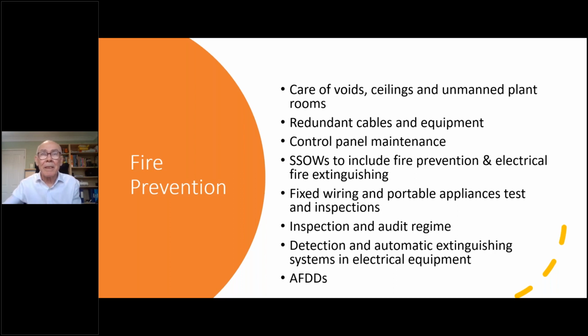So on fire prevention, a lot of what we can do, particularly in safe systems of work, is think about what the electrical maintenance staff can do, because a lot of fires start in void ceilings and within unmanned plant rooms, with so much redundant equipment and cables about, either live or dead, which adds to the problems. I'll show you some slides shortly on control panel maintenance.